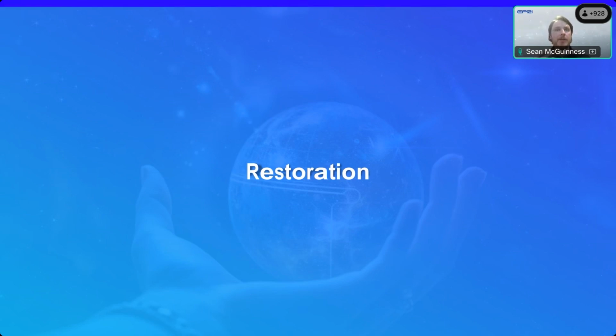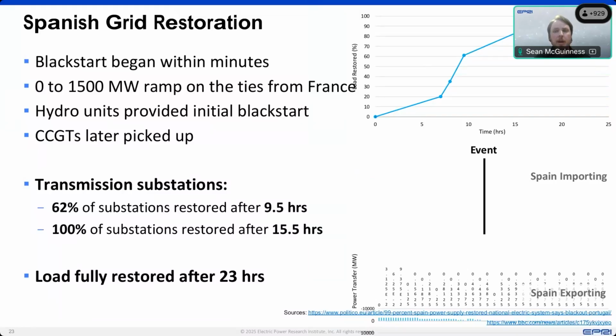Obviously, immediately after the blackout occurred, all of the system operators began to kick into restoration mode, assessing what was available, operating breakers, performing the switching, getting crews out to site, and so on. This is the information we have about the Spanish grid restoration. They pretty much began black start immediately, or within minutes. They began reconnecting the ties to France, which is a very rapid way to restore.